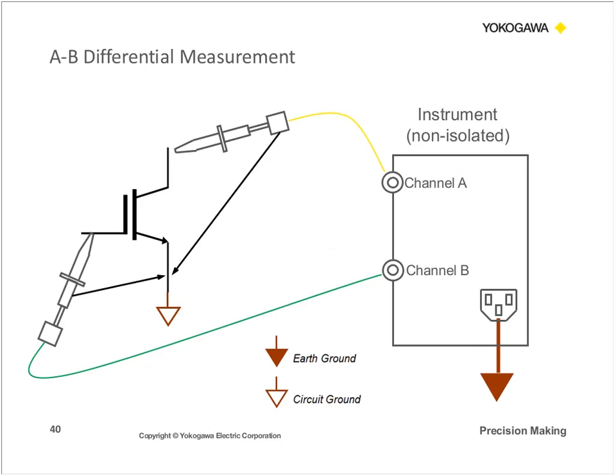One of the easier or more popular solutions that they implemented was the A minus B solution. Taking two passive voltage probes, both probes are referenced to the same ground point. The A probe measures the voltage at one point of the circuit, and then you have the B probe, which measures another voltage at a different point in the circuit. What you're trying to do is measure the voltage difference across A to B. This A to B technique was a simple method. Sometimes it got the job done, but it did not work well when there was high common mode voltage.